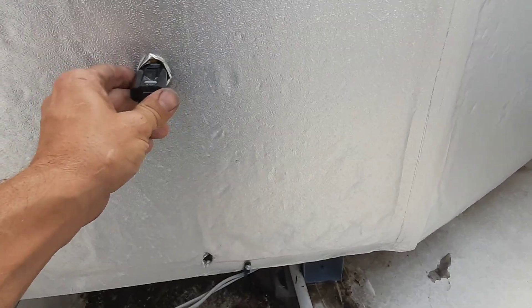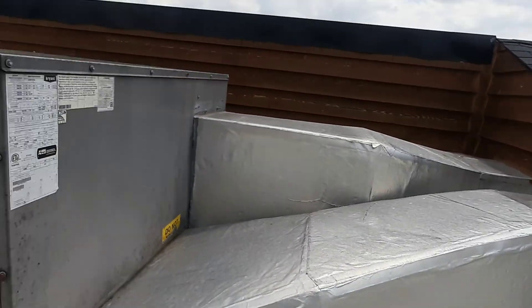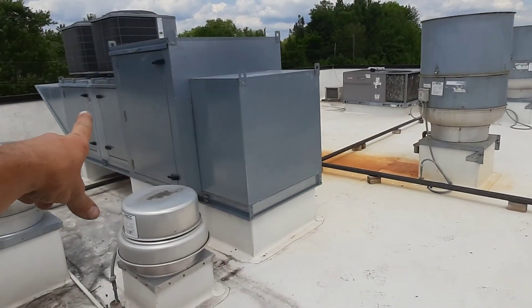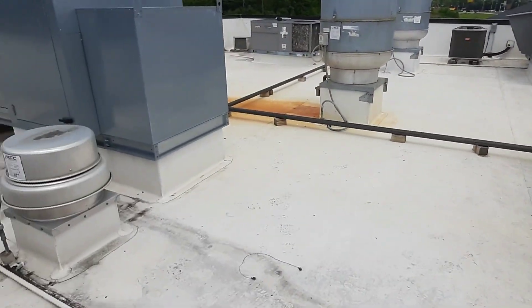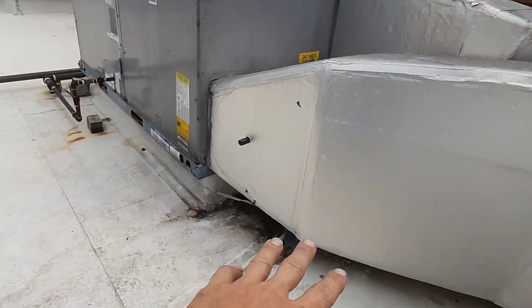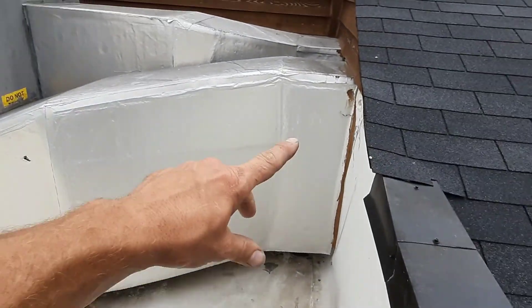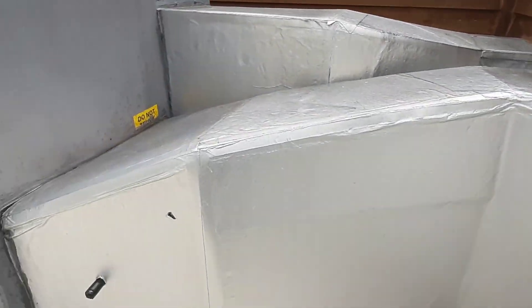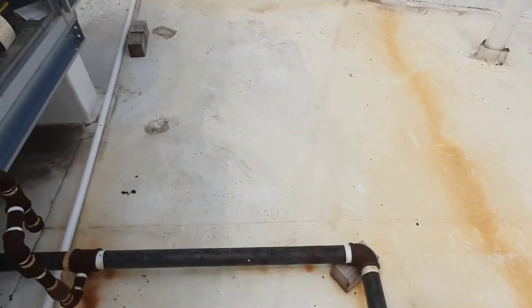Welcome to the restaurant world. We're going to check everything - keep it simple, don't overthink things. You've got dirty filters on the makeup air and it's going to cause all kinds of problems. I think all that humidity from the kitchen was rolling right out into the dining area. It's not a real big area, and we had condensating diffusers. One of the ACs was frozen up - I saw some ice in there. It's going to be just because of the dirty filters, which we've corrected.